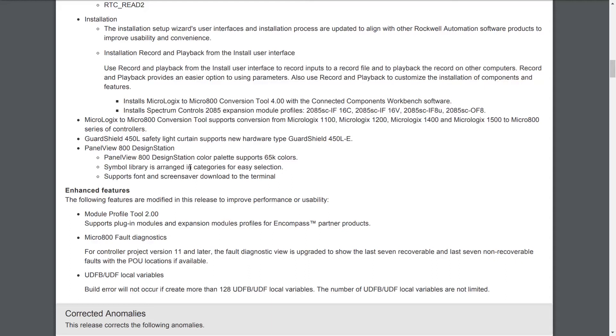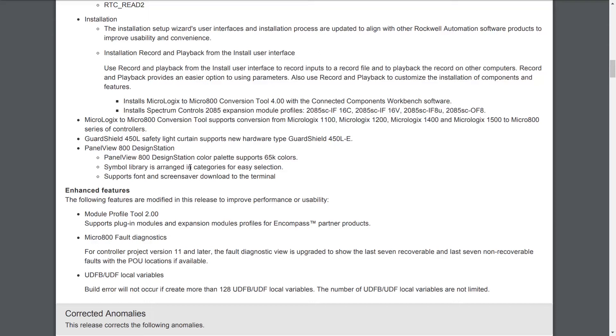As far as advanced features, they expanded the Module Profile tool to support plugin modules and expansion modules from third-party Encompass partners. They also expanded the Micro800 fault diagnostics so the diagnostic view will show the last seven recoverable and last seven non-recoverable faults with POU locations if available. When it comes to UDFB and UDF local variables, there used to be an error if you had more than 128. Now that's been eliminated and you have no limit other than memory on local variables in your user-defined function blocks or user-defined functions.